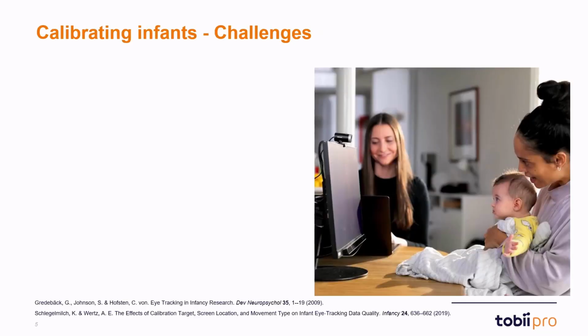So what are some of the challenges when calibrating infants specifically? One of the challenges comes with positioning and movements. In order to have a good calibration, it's important that the participant is correctly positioned and sits relatively still during calibration. This is, of course, a challenge with an infant that might move around or sit in their parent's lap while we conduct the calibration.